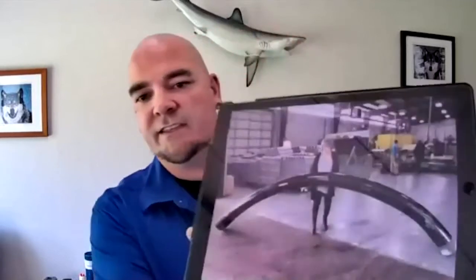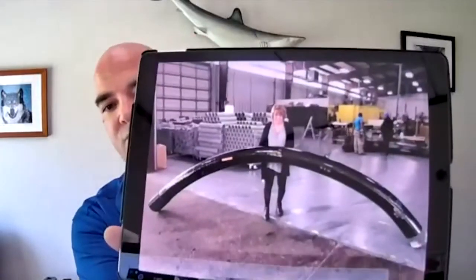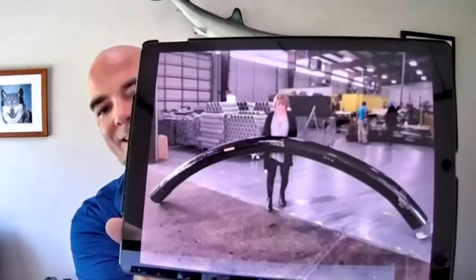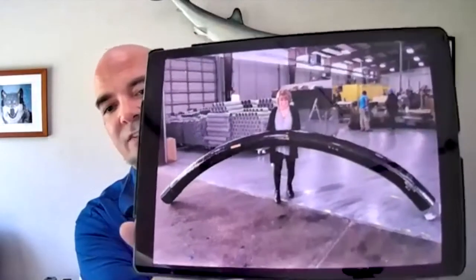As mentioned, they offer very lightweight and low installation costs. If you take a look at this picture right here, you'll see our office manager. She's holding up an 8-inch, 90 degree, 96-inch radius elbow. If that was steel, that would be well over 400 pounds. In fiberglass, it weighs a little more than 30. So our product brings tremendous savings from an installation standpoint.